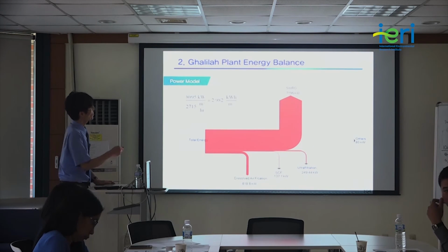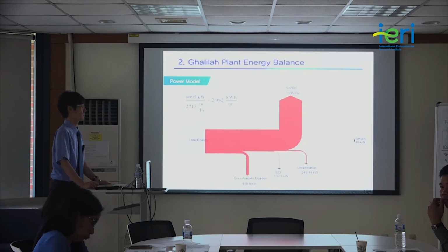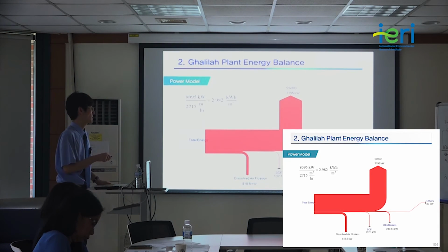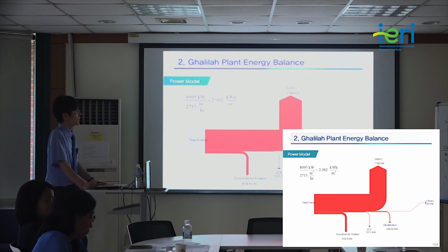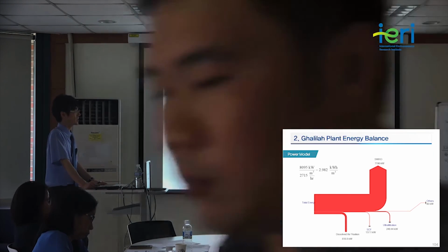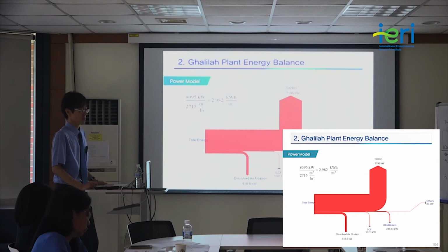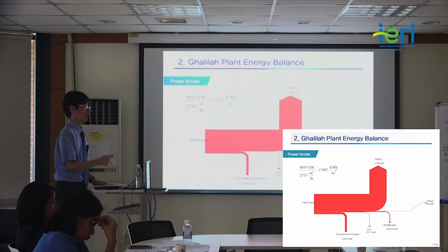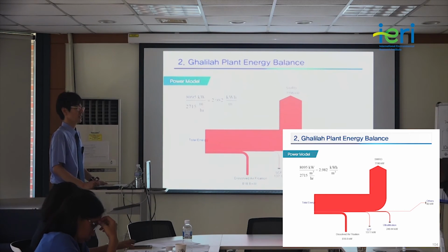And once we determine the energy consumption in a reverse osmosis system, we can also determine the energy consumption by other parts. And surprisingly, compared with other desalination plants, in the Ghalilah plant, the contribution of energy consumption by this seawater reverse osmosis is very large. So it accounts for more than 80% of the total energy consumption in the plant.